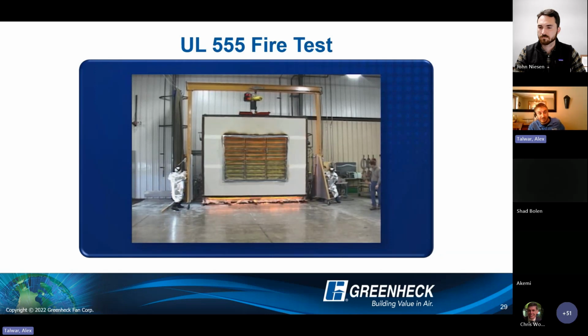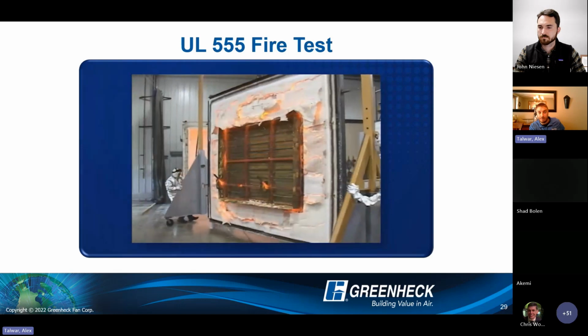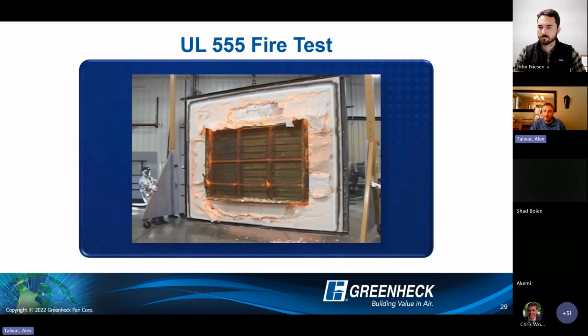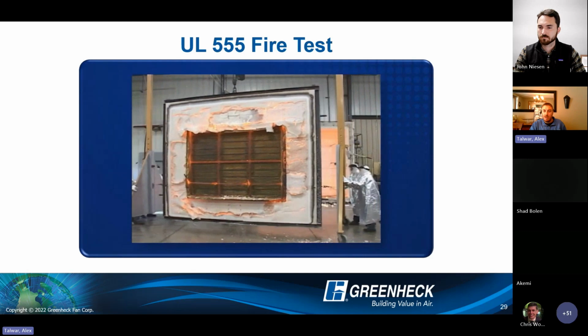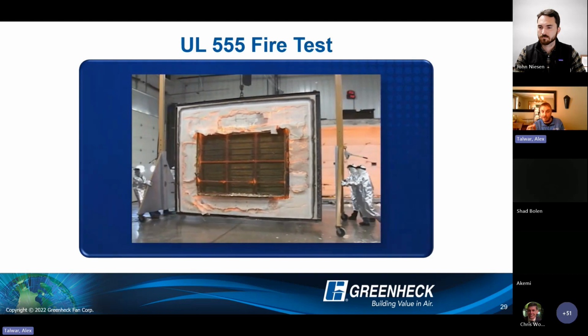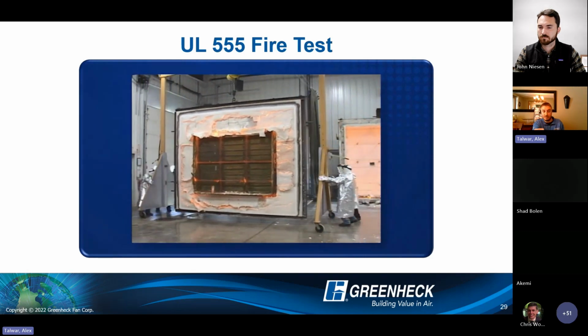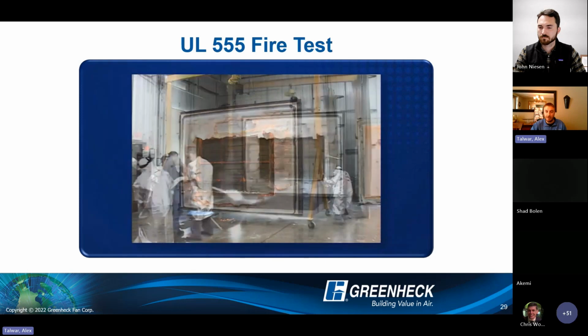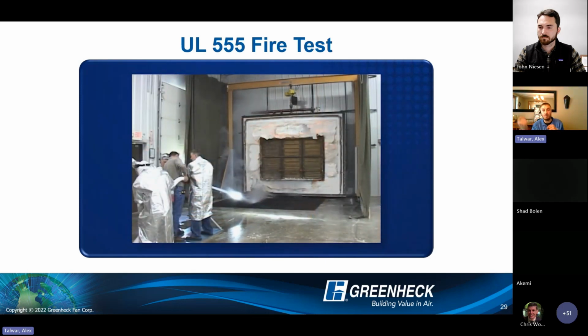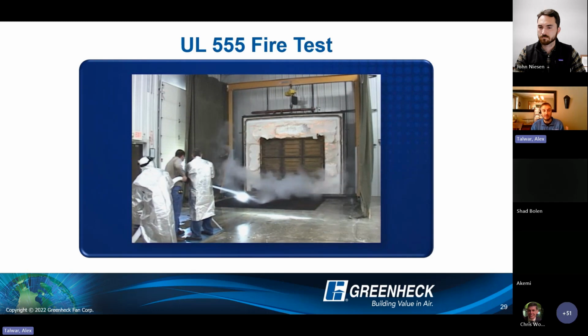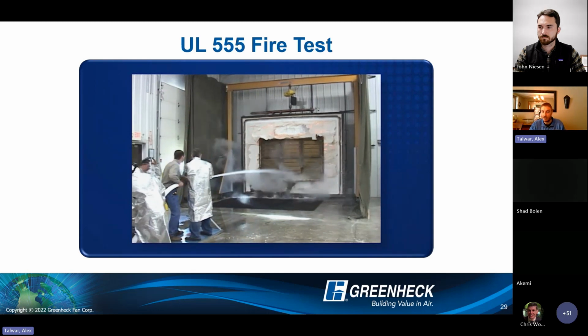So then after the test, this is after the exposure, 1.5 or 3 hours. This was probably a 1.5 one here. And we do have to test in both directions, right? These ratings are for both directions. So if you notice in the video here, multi-section damper, one row is facing one way, the other row is facing the other way. So it's a little bit of a 2-for-1 type test here.